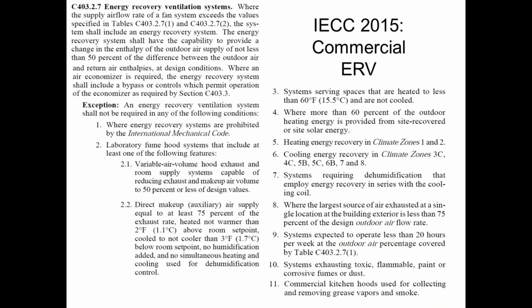There are times that this is code required. This language has not changed since the previous version. The tables have changed, but this language hasn't changed. The first thing to point out is that the ERV must be 50% enthalpy recovery, right? So if you have a sensible-only wheel or sensible-only plate, you're going to get a certain percentage on the sensible side and you're going to get 0 on the latent. So when it comes to averaging out the total enthalpy, you're not going to be able to comply. You cannot put in sensible-only wheels or plates. You have to use enthalpy wheels or enthalpy plates in order to accomplish this.